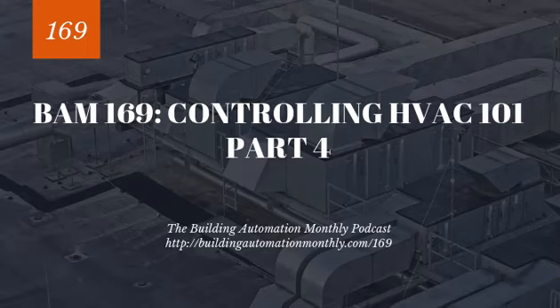And finally, hot water supply set point. So there are kind of three ways you can do this. There's controlling the firing rate of the boiler. This is the most common, but it's also the one I don't recommend because it's not for newer techs. It's the one that's most difficult to figure out, especially if you're working with resistors and you don't have a simple 0 to 10 volt interface. You can control the set point via 2-wire control if it supports that. If the control panel supports that, that is my recommended method. And then a lot of newer boilers have interface cards, so you could use BACnet or LON or Modbus.